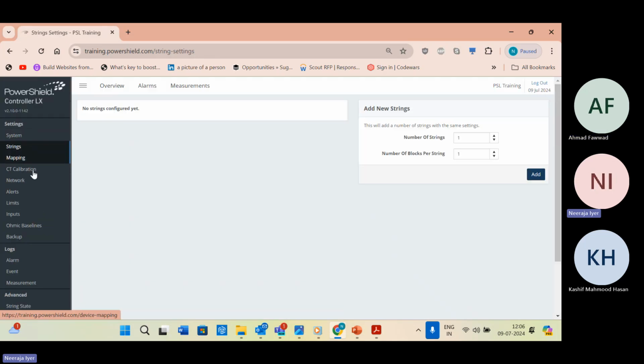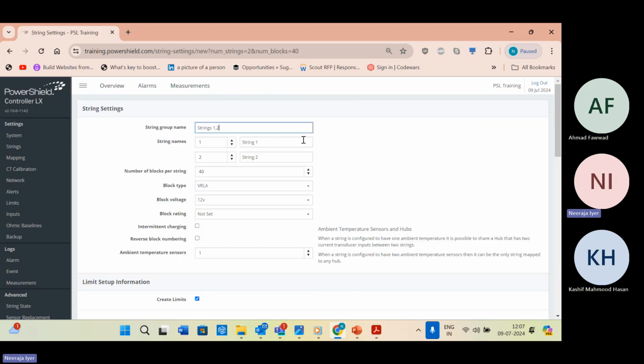Then there are the strings. What I recommend is you have two strings, and the number of blocks per string is 40, correct? Yes. Because we are just going to add this, we will start with this for testing purposes, because you're configuring it for the first time. So there's string 1 and string 2. We have 40 blocks. The battery type is VRLA. We have other options, but VRLA 12 volts.